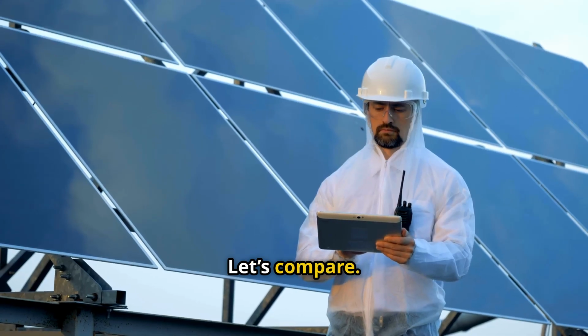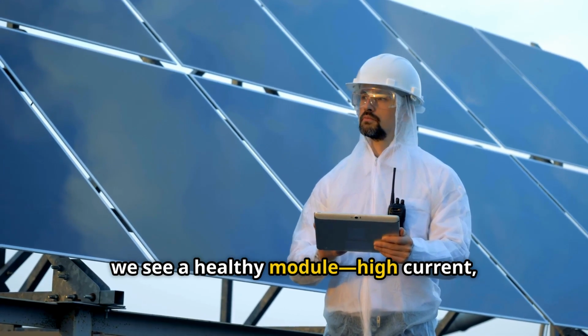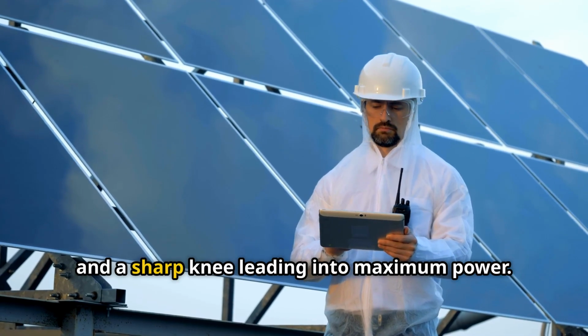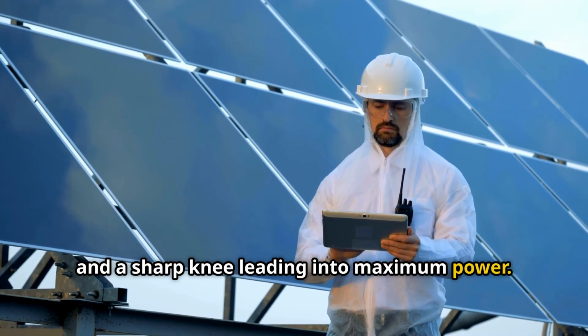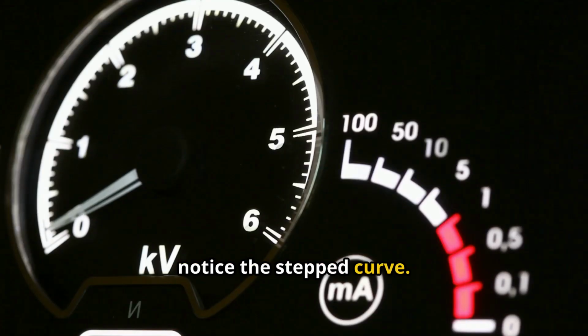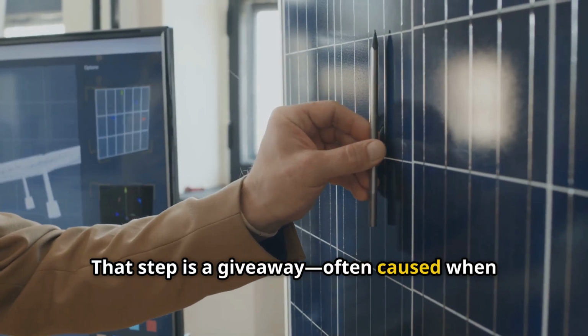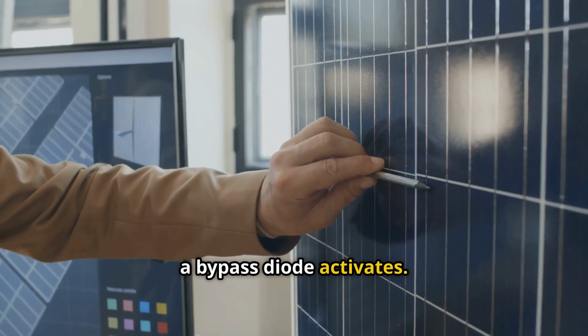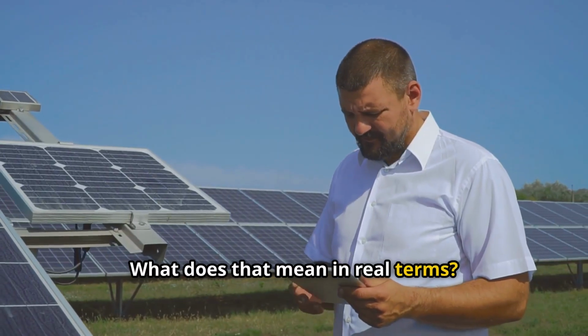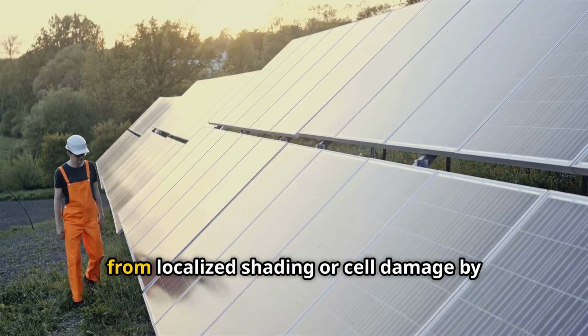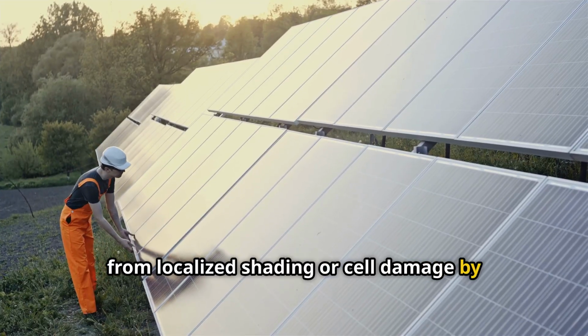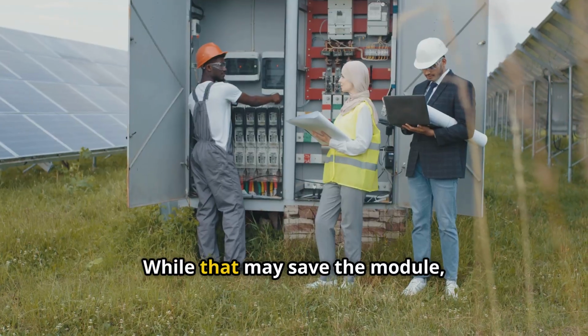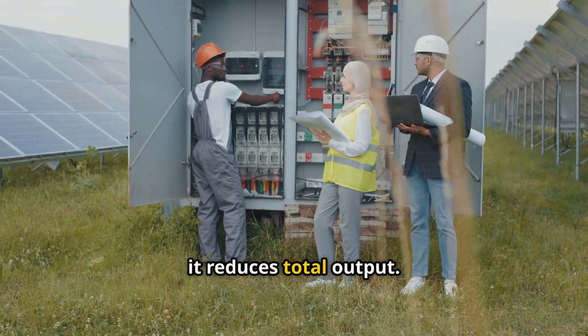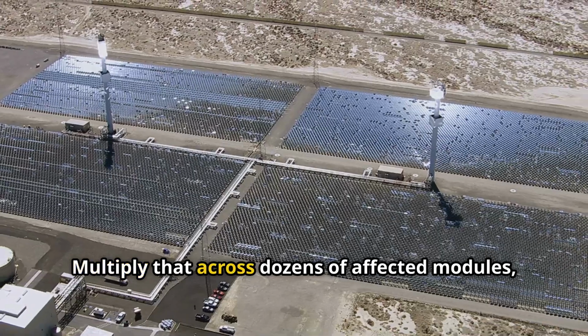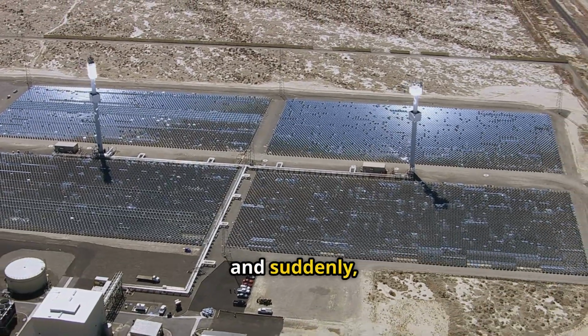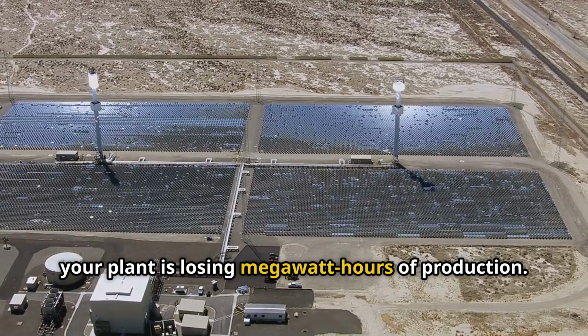Let's compare. On the left, we see a healthy module. High current, stable performance, and a sharp knee leading into maximum power. On the right, notice the stepped curve. That step is a giveaway, often caused when a bypass diode activates. What does that mean in real terms? It means the module is protecting itself from localized shading or cell damage by redirecting current. While that may save the module, it reduces total output. Multiply that across dozens of affected modules, and suddenly your plant is losing megawatt hours of production.